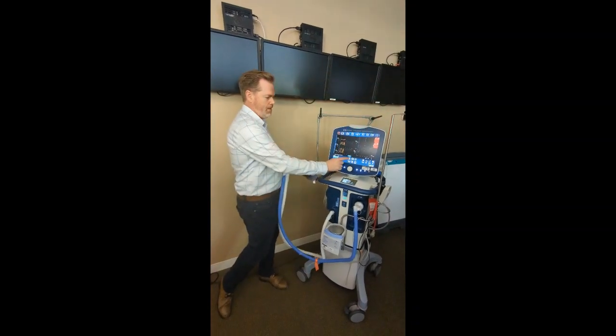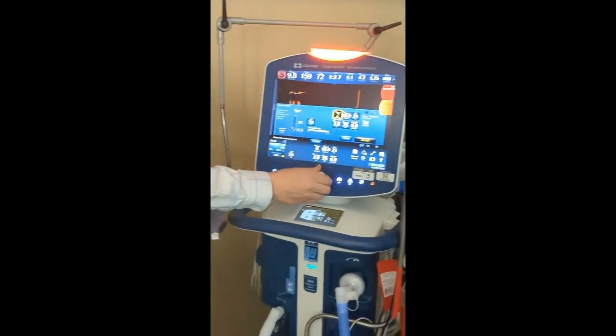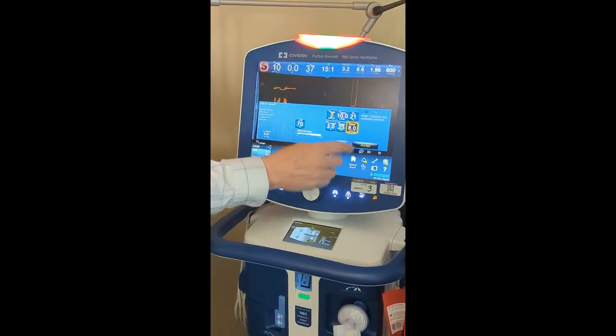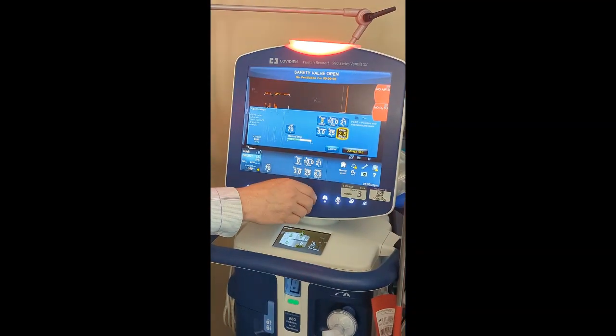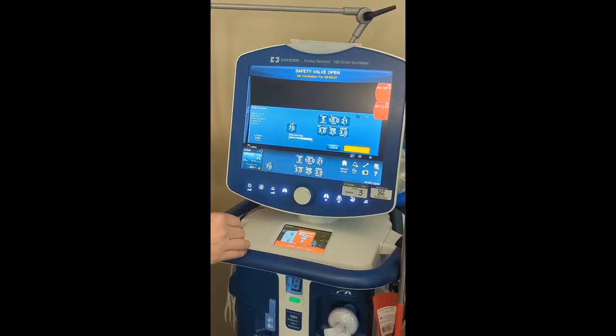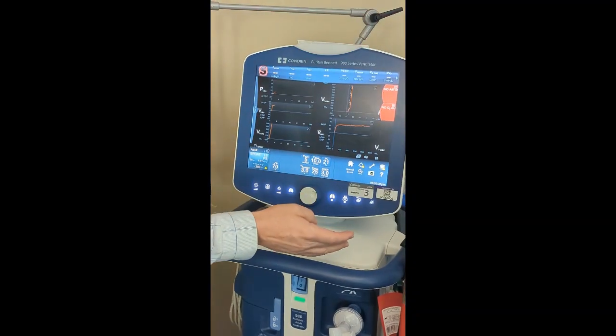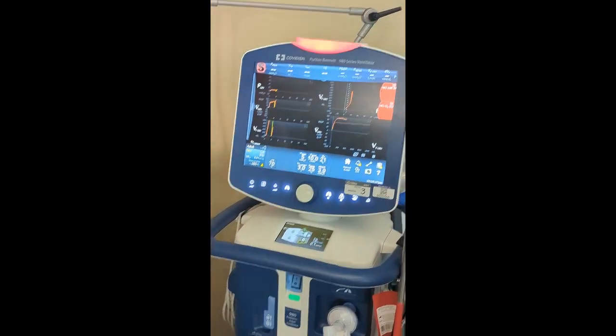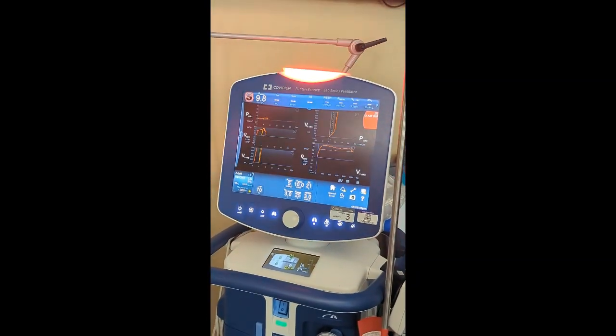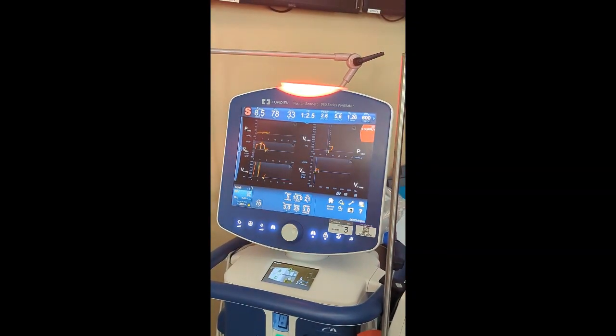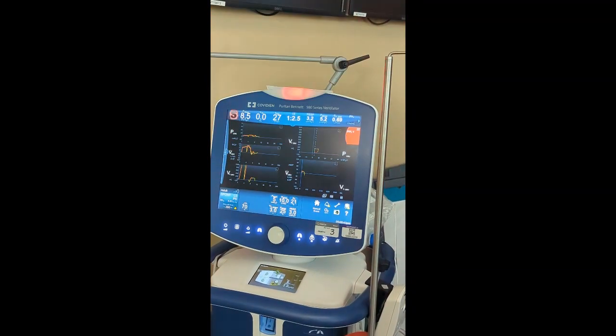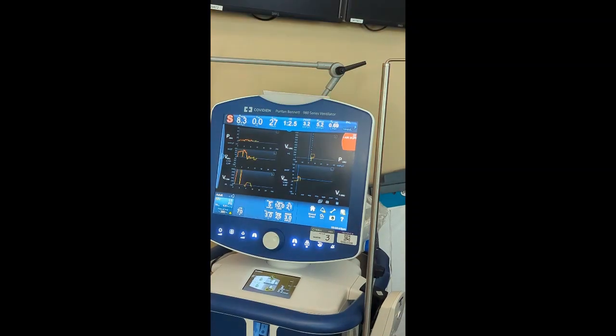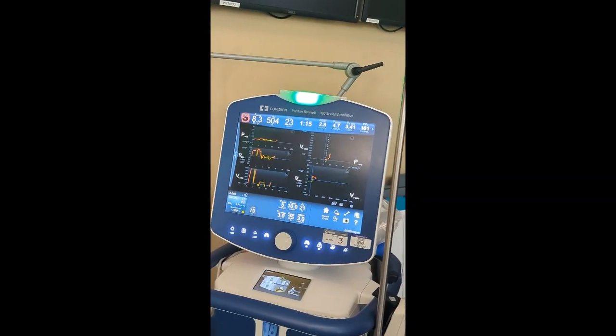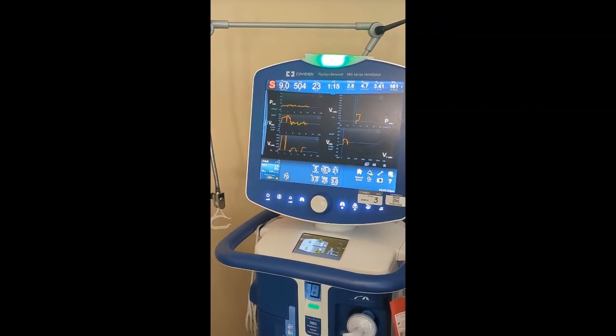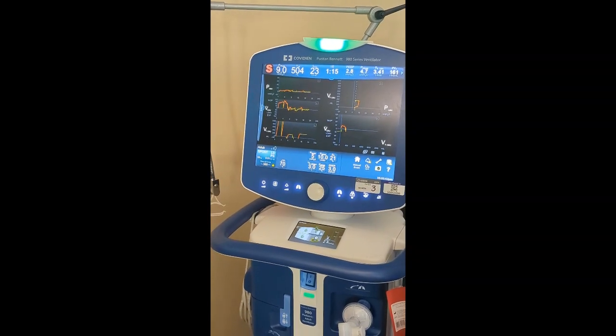So right now the cylinder actually talks, it has two-way communication with a transceiver mounted above it. So it's double checking the concentration, it's double checking the expiration date, even though I asked you all to do that, it's also doing that behind the scenes. There's a black cable, I just wanna make sure that black cable is connected. It has no air supply. Yeah, this is the one. And then I have my blender oxygen hose to my high pressure oxygen source.